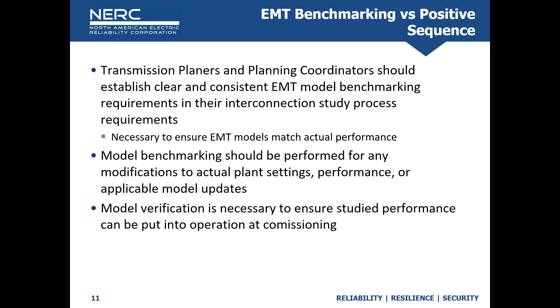Verification, as we're using it now, is slightly different from validation. Validation is taking the models and putting them on top of each other—do they match? Verification is more like: is the same parameter in the product as in the model? Are they the same units? Do they do the same thing in the code? If you're doing detailed interconnection studies and there's a stability issue that you mitigate with tuning, how do you get that into the field? You need some sort of mapping, verification, or attestation that the performance you tuned for in your planning study actually gets put into operation—otherwise you're just plugging unknowns into the grid until one of them is too unknown and something bad happens.